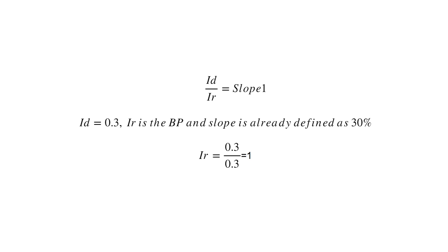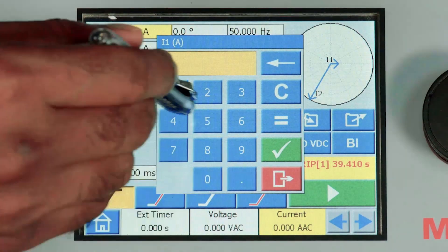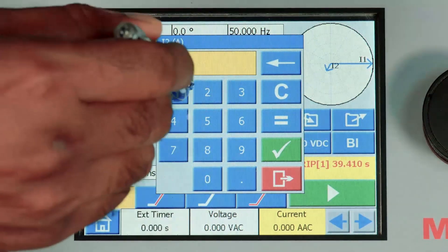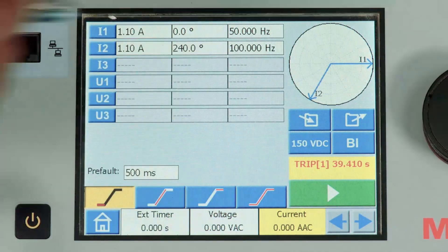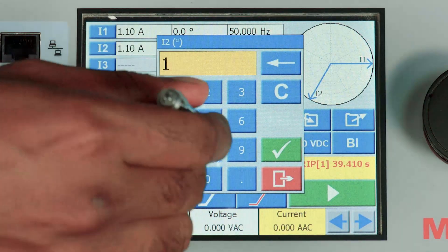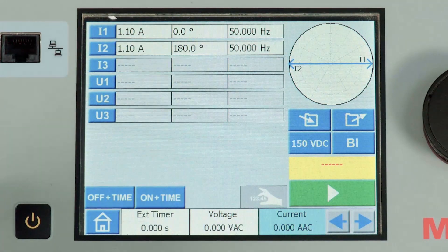Between 1 per unit and 1.5 per unit, the slope is 30%. To verify the same, let us inject 1.1 angle 0 in HV and 1.1 angle 180 degree in LV. The current value is chosen more than the initial point. So let me inject this value.